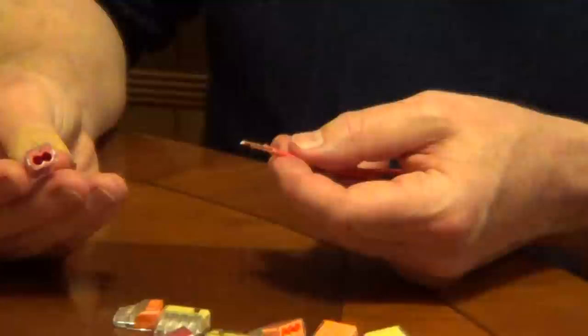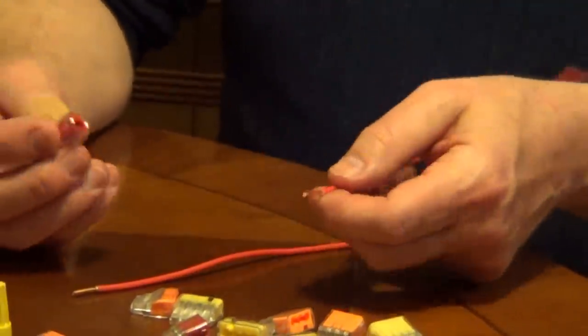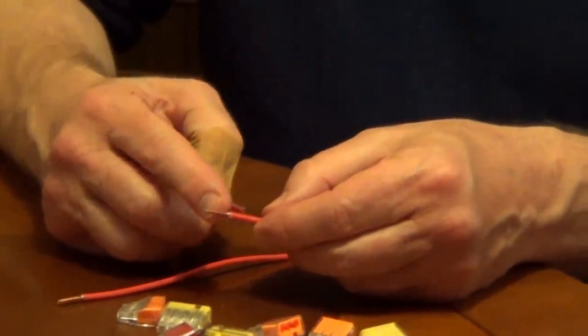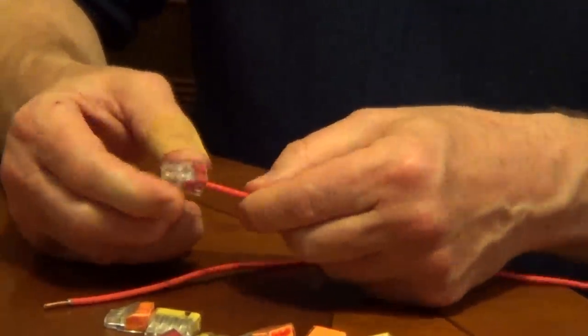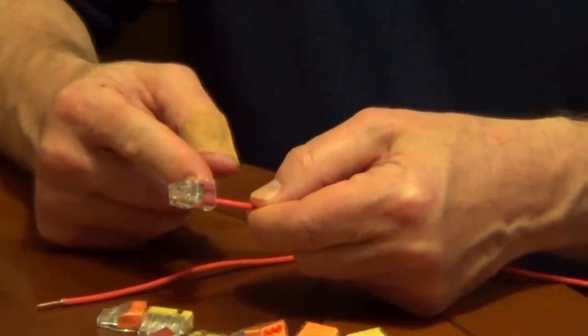What is nice about these stab connectors is you just push it straight in. You want to strip your wire half an inch and you just push it straight in. It does a fantastic job of grabbing it.